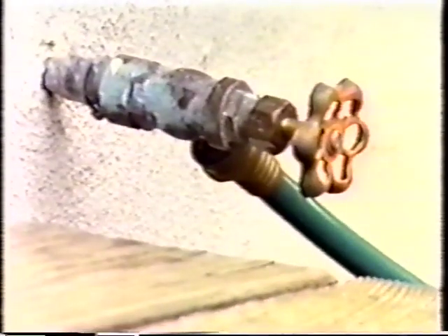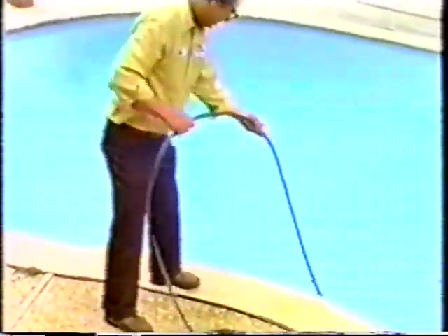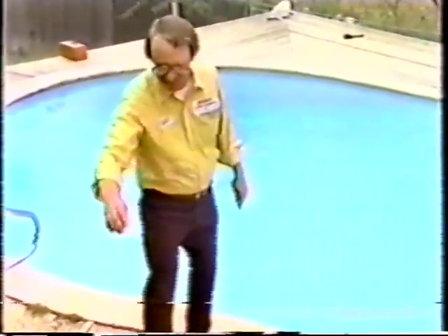The tap is open. Say that his wife or one of his kids inside the house decides that they want a drink of water. Now we have a classic example of a cross connection. They turn on the faucet. They're not going to get water from the water main. They're going to get water from the bottom of the swimming pool. It's going to be siphoned up and into the house. All he's going to get is the water sucked up from the bottom of the swimming pool, which includes chlorine and acids or whatever chemicals you can think of.